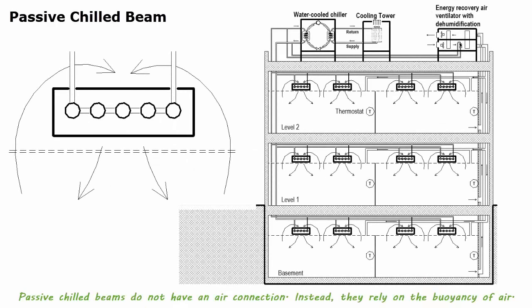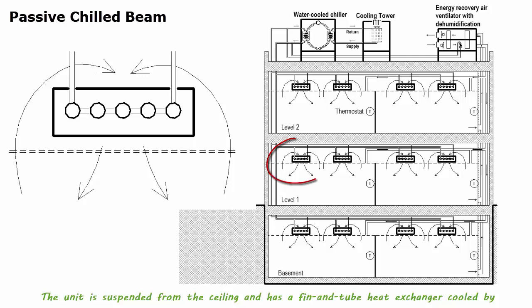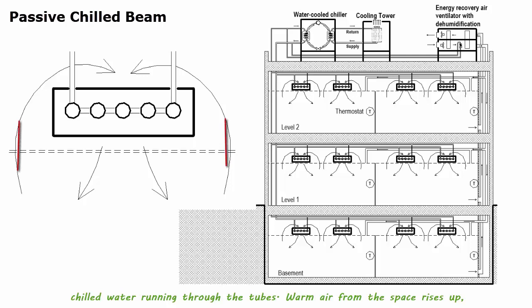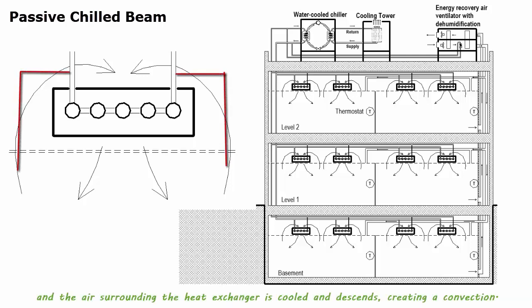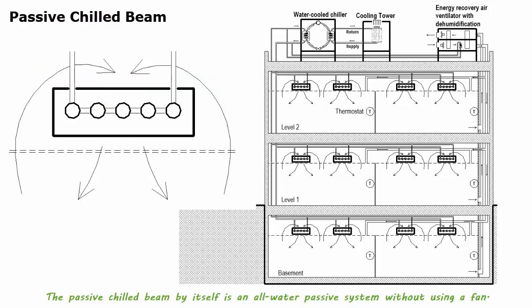Passive chill beams do not have an air connection. Instead, they rely on buoyancy of air. The unit is suspended from the ceiling and has a fin and tube heat exchanger cooled by chilled water running through the tubes. Warm air from the space rises up, and the air surrounding the heat exchanger is cooled and descends, creating a convection. The passive chill beam by itself is an all-water passive system without using a fan.